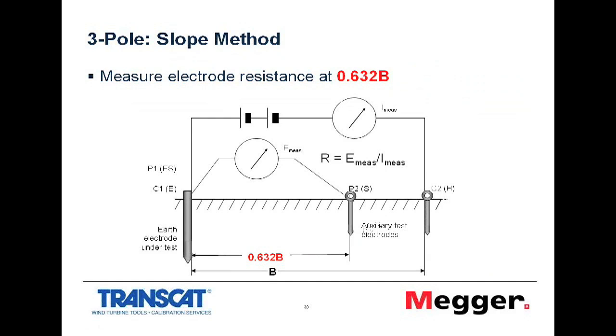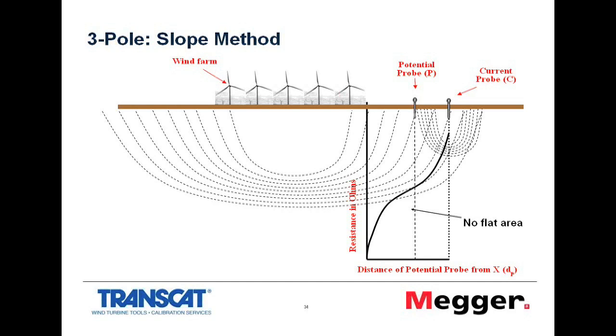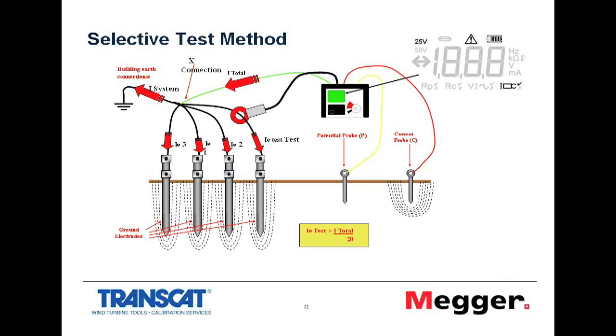Now the issue becomes greater if we're going to test a whole wind farm. Wind farms are obviously huge systems, and I've actually heard of people running out 2 kilometers plus of cable to be able to take a measurement. In our application department, we did have an inquiry once where somebody was actually using 2 kilometers of cable. In this case, it is very doubtful whether you'd be able to get anywhere near that kind of distance practically to take a measurement. So the slope method would come into its own.